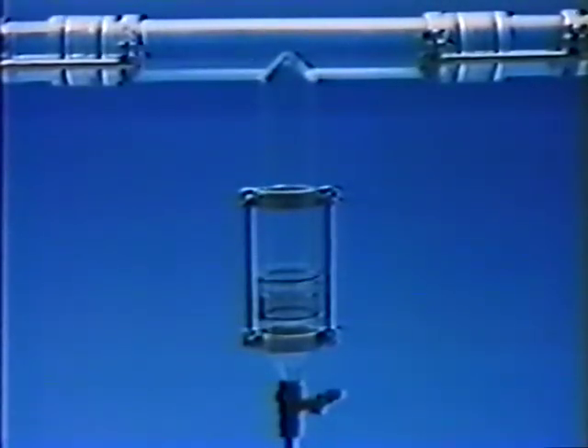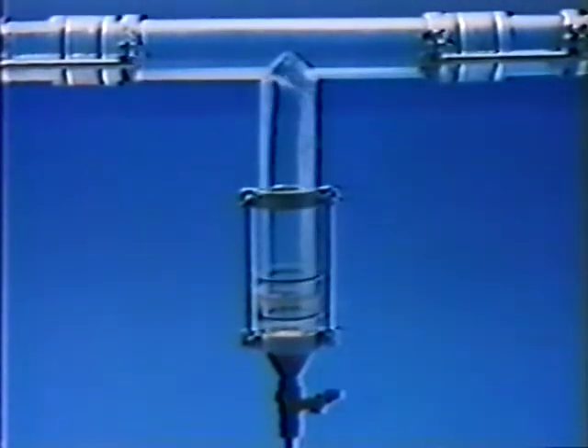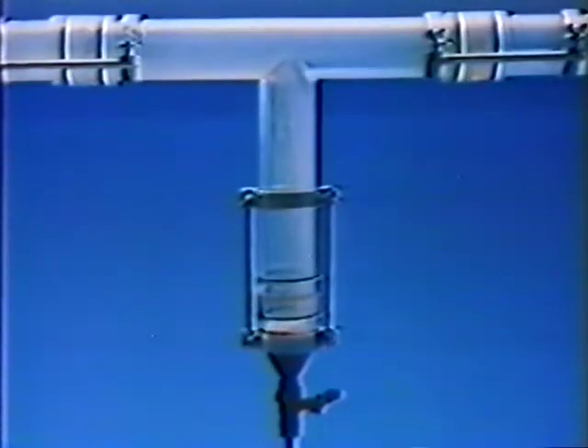A simple device to catch liquid in gas pipelines is the siphon trap, an opening in the bottom of the pipeline in which the condensate collects. The siphon trap functions effectively as long as the liquid flows along the bottom of the pipe. As soon as annular flow occurs, the catching efficiency rapidly deteriorates.